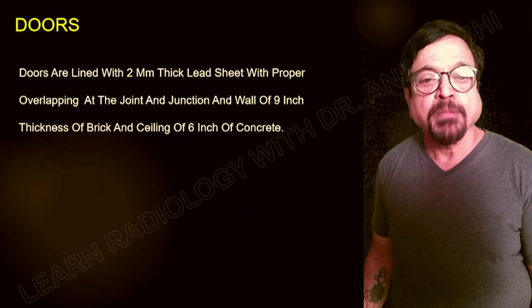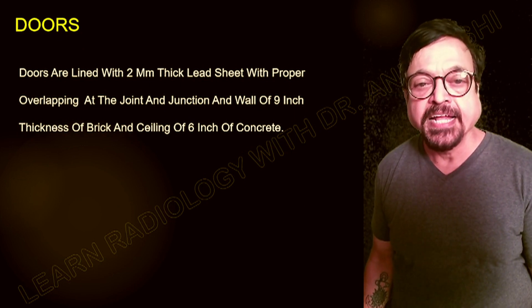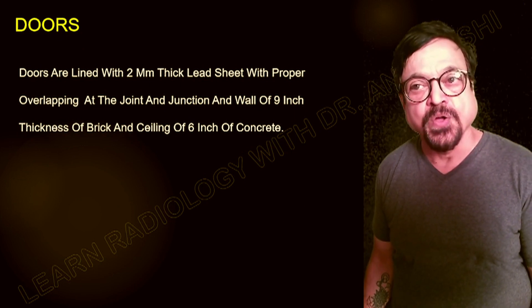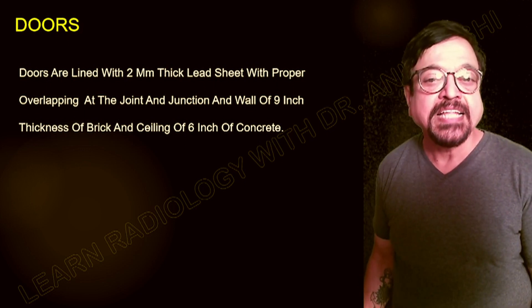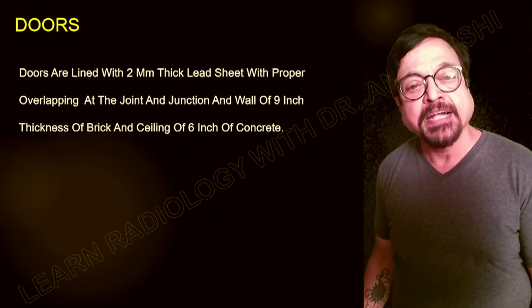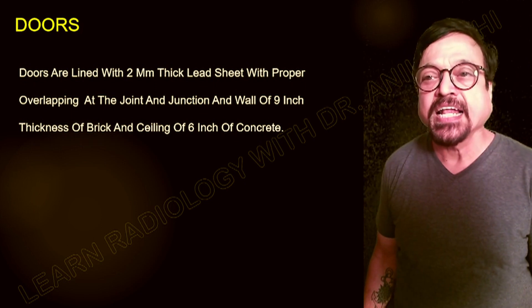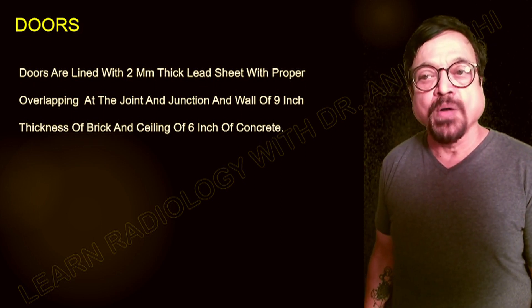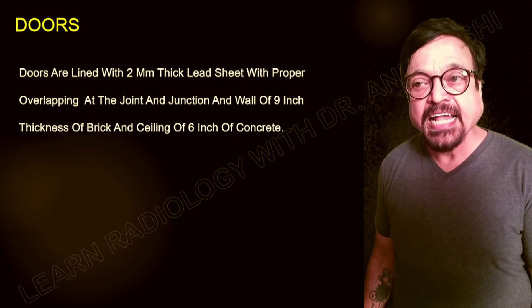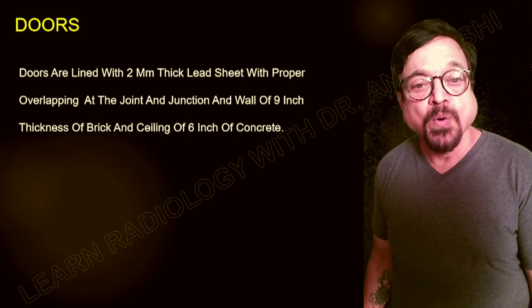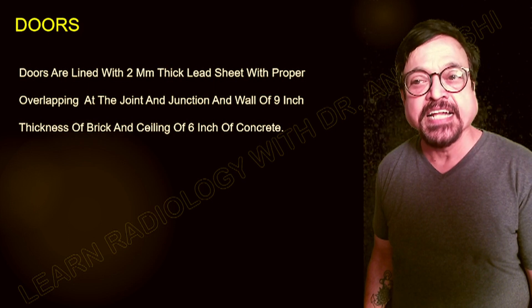Doors are also important. Patients should not be opening the door during an exposure — the door has to be locked when radiation is being generated. The doors are lined with 2 mm thick lead sheets with proper overlapping at the junction, along with 9-inch thick walls. Proper overlapping is critical; otherwise, gaps will result in leakage of radiation.